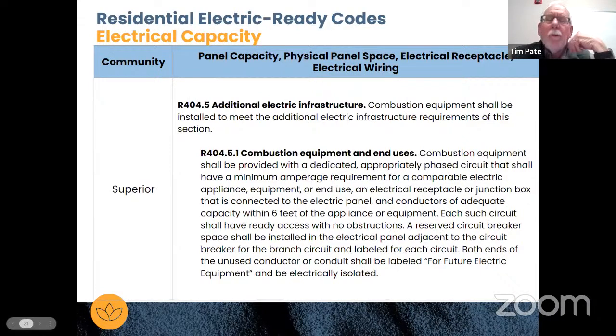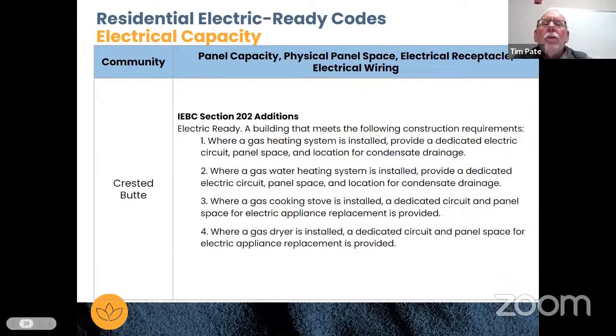Thanks. This relates to my earlier comment about PV ready and conduit installation. It seems the intent of this legislation was to make future retrofits the least costly. So just providing space in the panel board and maybe space for a 2-pole breaker still means you'd need an electrician, and electricians are good at fishing and pulling wires through a house, but that's an expensive proposition—I know from experience with old houses I've bought. My suggestion is that beyond panel board space, we also provide the wiring, similar to EV readiness, and maybe just a junction box to a particular location.